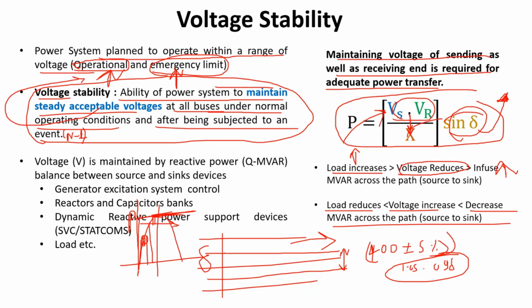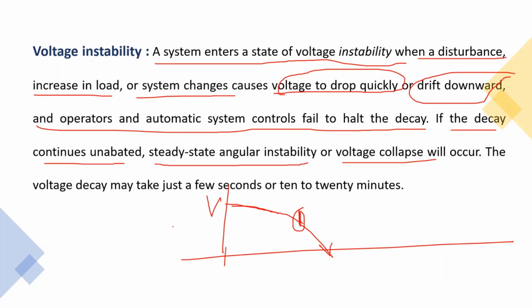Your system is not able to maintain the voltage. Your generator is not able to maintain the voltage. Its load angle has already reached its own limit. And if you try to infuse any more, if you reduce the voltage any further, immediately the generator will go out of step basically. So you basically go out of synchronism and there is a voltage collapse. When generators go out of synchronism, there is no generation in the system. Voltage will start decreasing and there is an immediate collapse that will happen in the system.